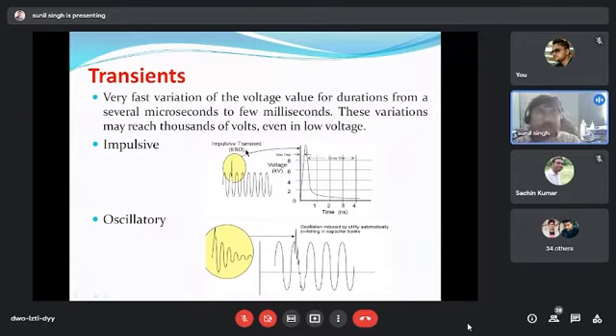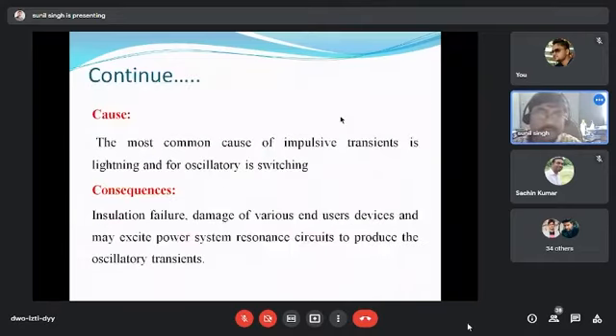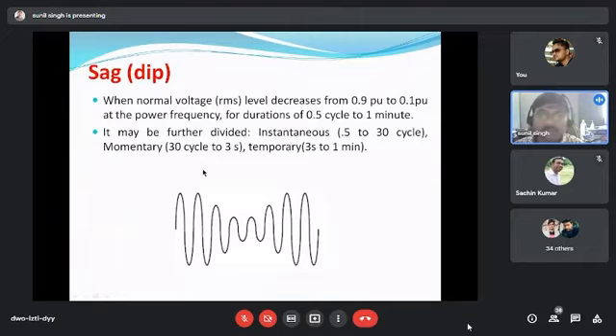Impulsive transient means, what is the reason for an impulsive transient? That is the lightning, also known as the lightning transient, or it may be a switching transient. So transient over voltage in electrical engineering can be classified as lightning over voltage or switching over voltage. Lightning over voltage means due to the lightning, and switching over voltage means due to the switching operation of the circuit breaker. So these are the transients. What are the main causes of the transients? As we know from the name, lightning and switching are the main causes of the transient.